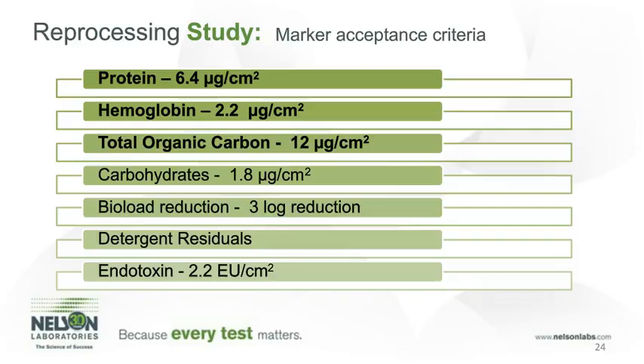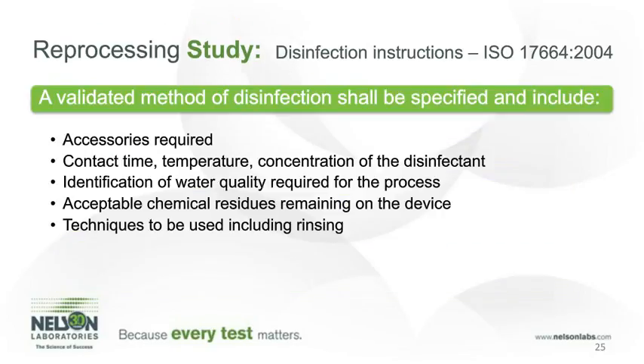Next, we'll be discussing disinfection instructions and validations. Again, ISO 17664 is an important standard regarding disinfection validations, and a validated method of disinfection shall be specified. Items that need to be included are all the accessories required, the contact time, temperature, and concentration of the disinfectant, the specific water quality that is required for specifically the final rinse, and that should be more of a critical water supply. We also need to determine if there are any chemical residues left on the devices after the rinsing is performed.